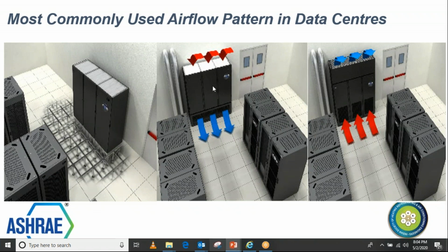And then this one is a front discharge unit, which discharges cold air from the front side. Here you can see that there are grills and fans, so maybe the same unit is lifted above the floor, or there are units available in the market with a factory built-in provision in front of the unit, which can discharge the cold air from the bottom front. In such a case, you do not require an access floor or raised floor. You can just throw the cold air in front of the servers or the VFD panels in the panel room or control room, and it extracts the heat, and the hot air comes back on the top. So this can also be followed in a layout where it is feasible from the airflow pattern point of view. So it is important to study the layout before going for this kind of solution.